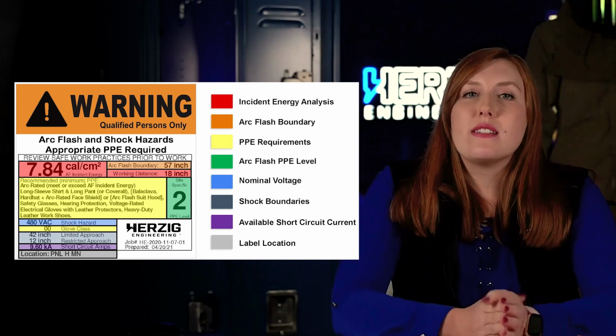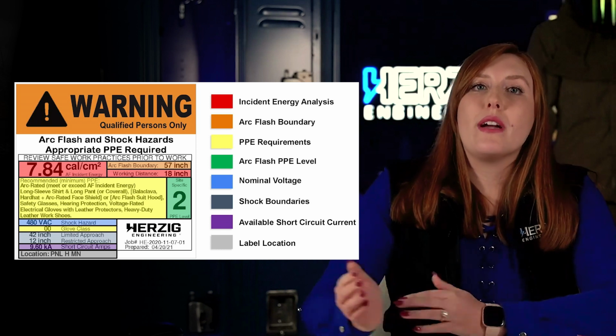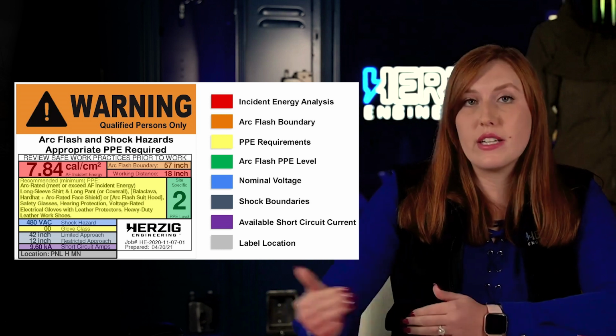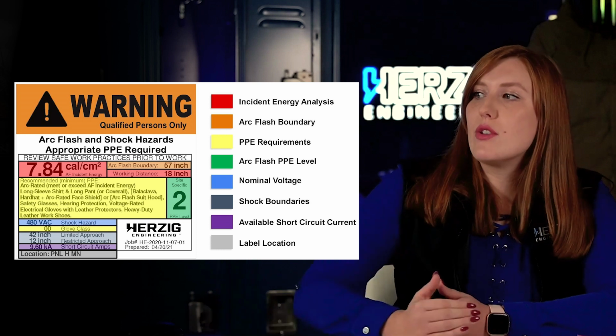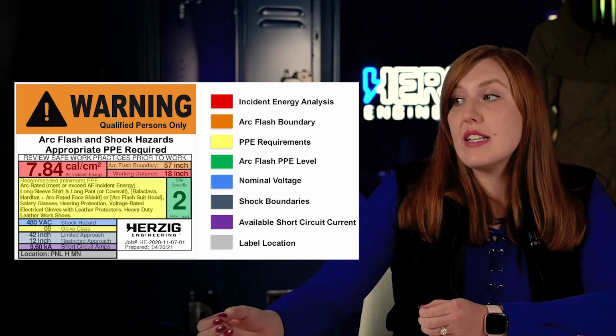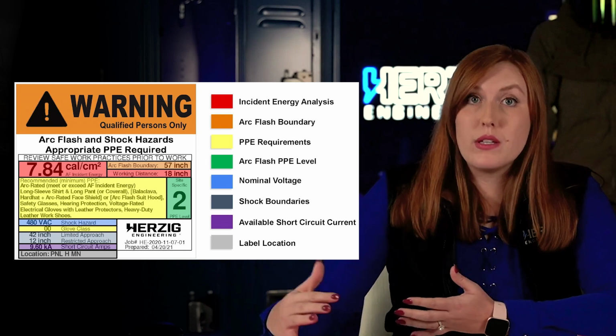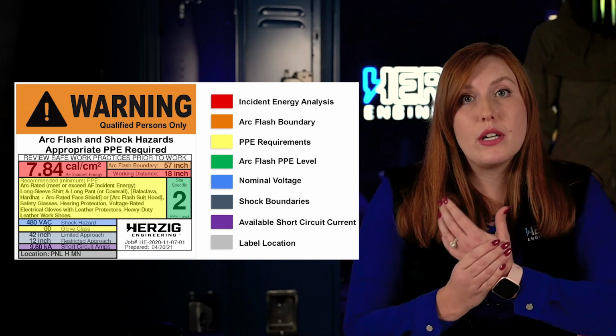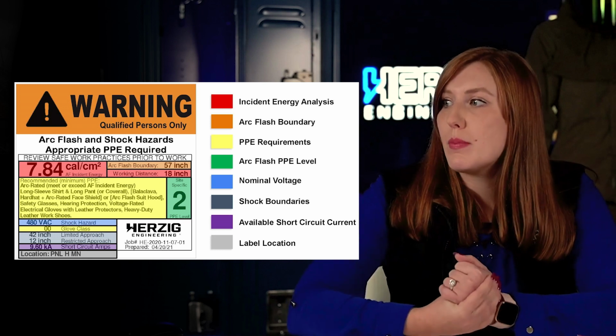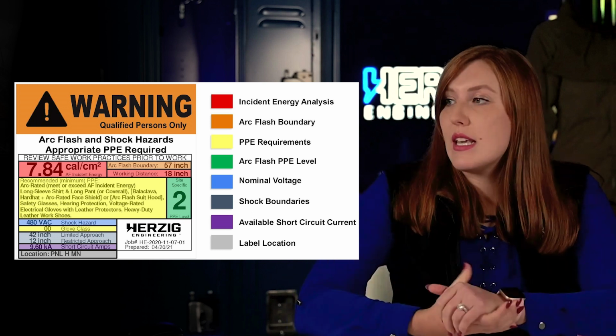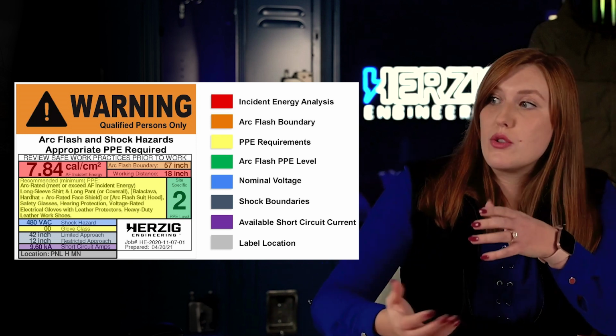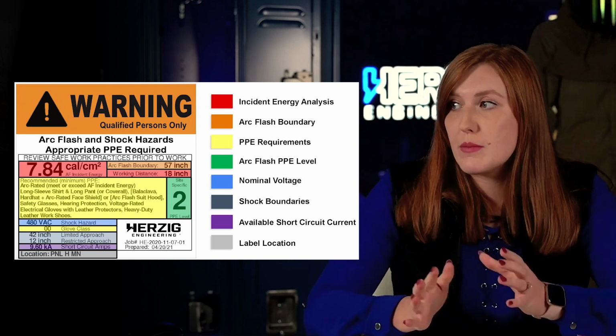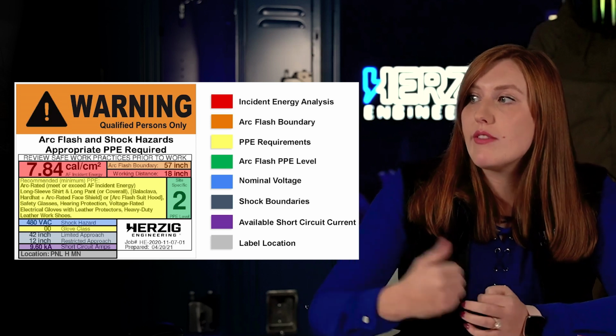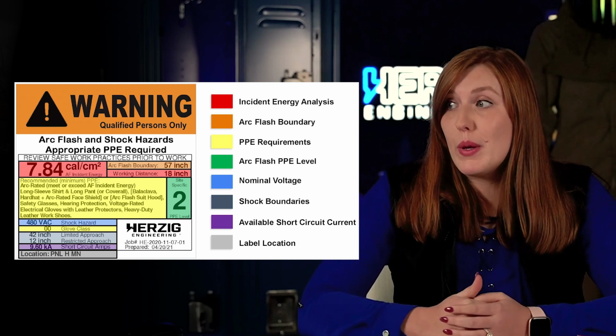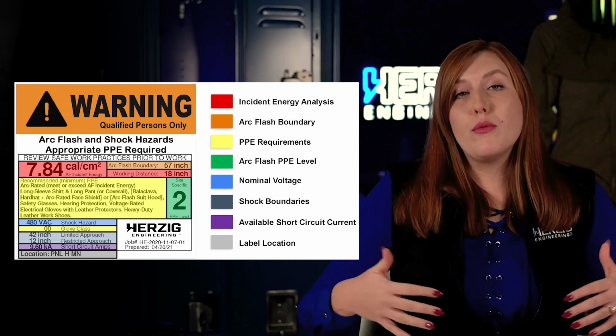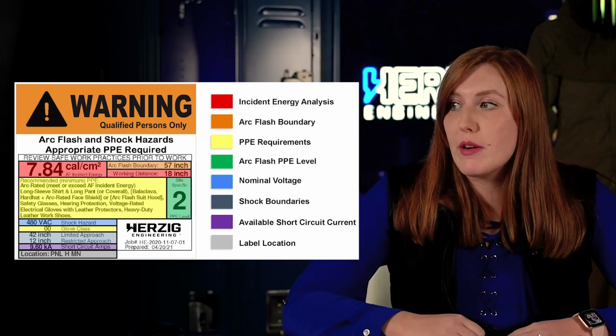Another important part of this is not just the arc flash hazard, though. You also need to be aware of the shock hazard. That is something that hurts and kills people even more often. And so knowing the highest nominal voltage you're facing and what the boundaries are for that, as well as the glove class you need to wear, the rubber gloves that go on your hand to keep you isolated from that energized circuit. And then the boundaries keep people out. This one shows a 42-inch limited approach boundary, which is pretty much set for low voltage equipment. The arc flash boundary is 57 inches. So we would want to set up our barriers or our barricades out to 57 or more inches away from the equipment.